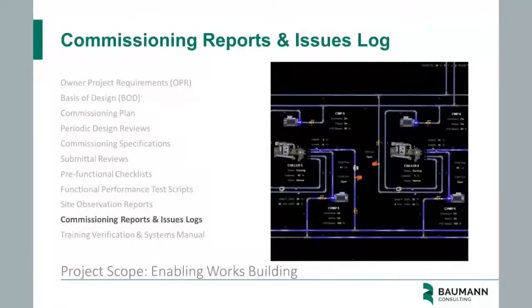This is a close-up of chillers 5 and 6, which are the new chillers that would actually handle the base load. They're the lead chillers. The other chillers, which are existing - chillers 1, 2, 3, and 4 - were relocated to the energy center and connected to this loop. They will serve the additional capacity as lag chillers.